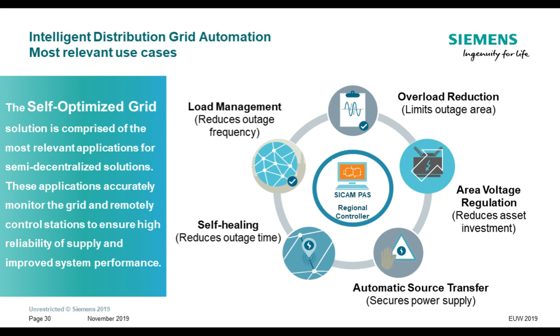This mainly includes reduction of outage time by self-healing, load management, overload reduction, area voltage regulation to control voltages in a certain region, and automatic source transfer - so if one of the transformers goes out of service, we can automatically switch over to the most healthy part.